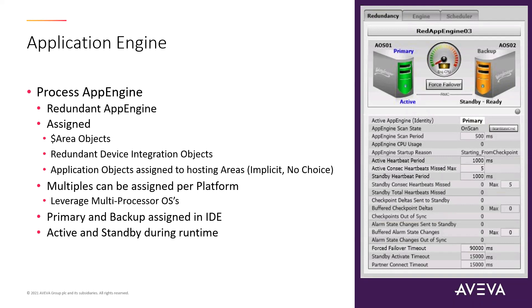When we configure these engines, there's a primary and a backup which we assign in the IDE, and they become active and standby during runtime. The primary is the one we do all the configuration on. The backup is slaved to the primary from a configuration perspective, but either one can become active and either one can become standby.